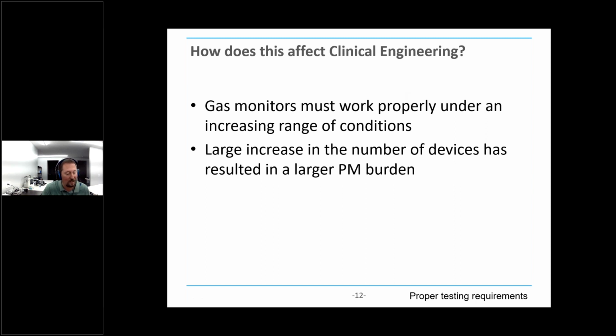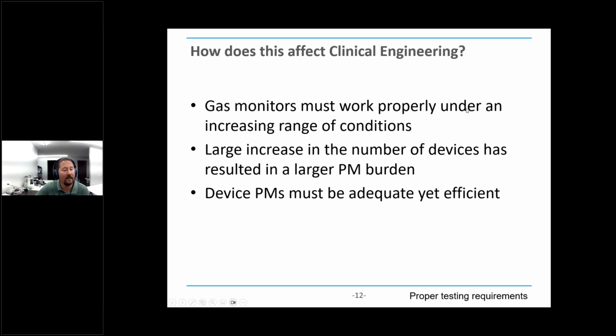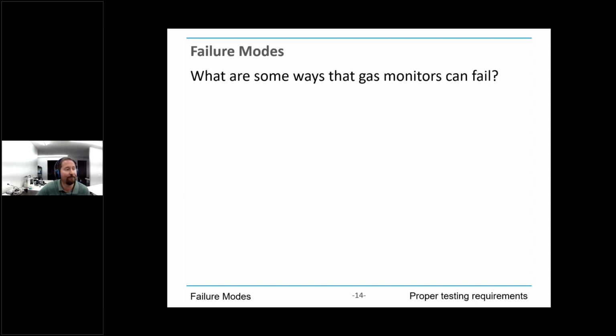We've seen hospitals that have 150 different capnometers, and not only are their numbers large, but the models are also large, because now instead of having 1 or 2 models, you might have 5 or 6 different models that you have to test or do PMs on. And so really your PMs do need to be adequate. They need to do a good job, but you got to be efficient at it, which is why we developed the SmartTank.